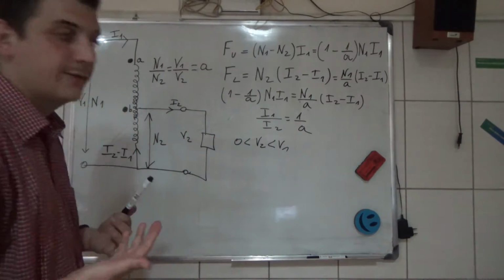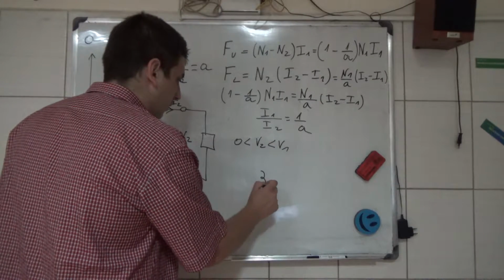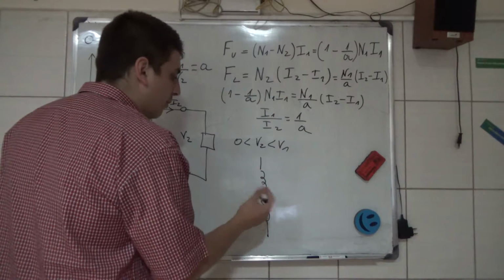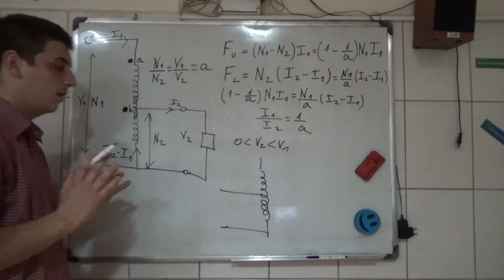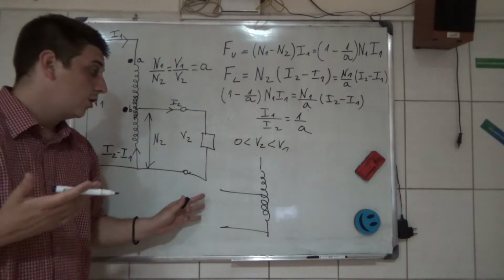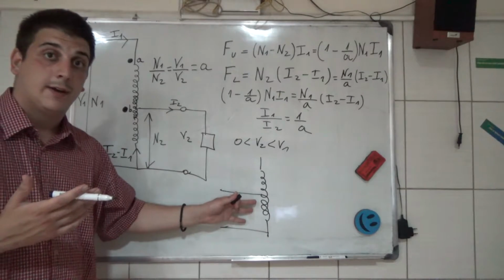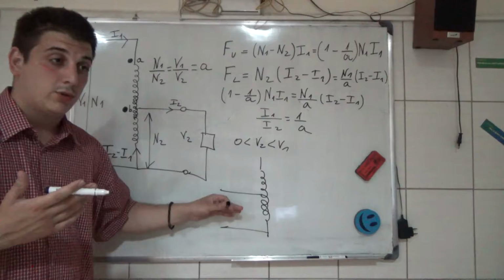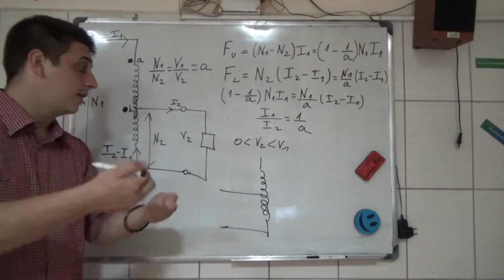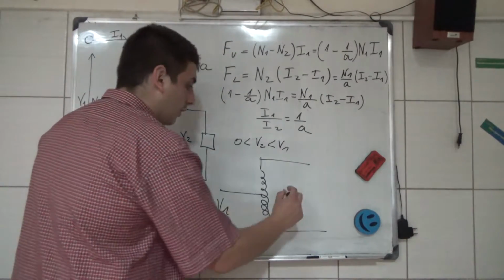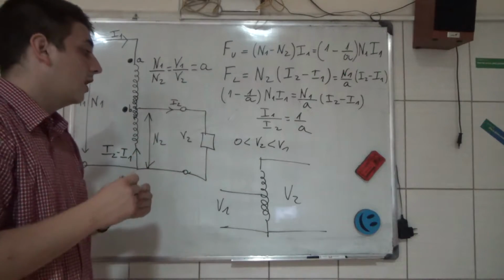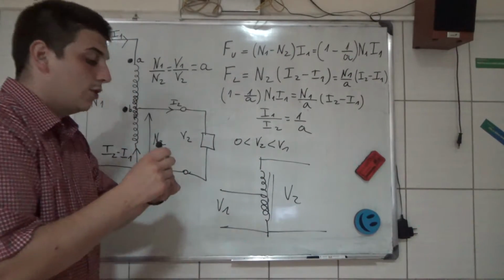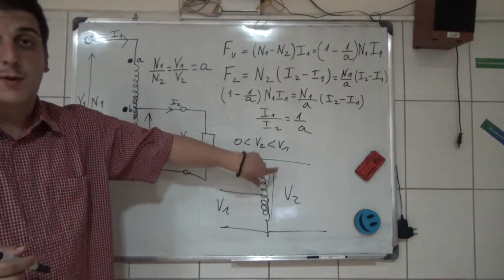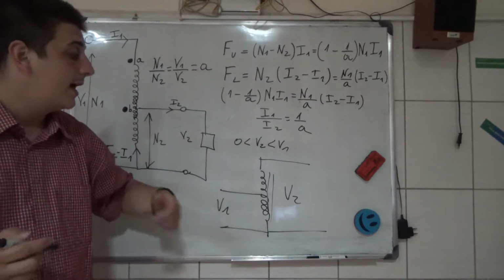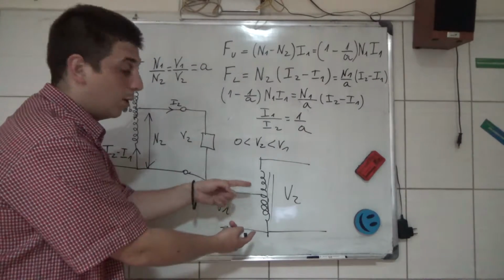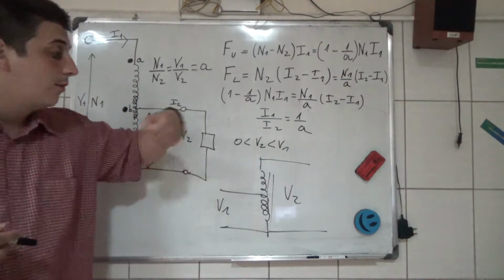However, if you had an autotransformer like this, and we brought the primary voltage to the lower half, and put the secondary terminals here and here, then this is a step up, because with the same flux in the ferromagnetic material, more winding obtained on the secondary than on the primary means the voltage is going to be higher.